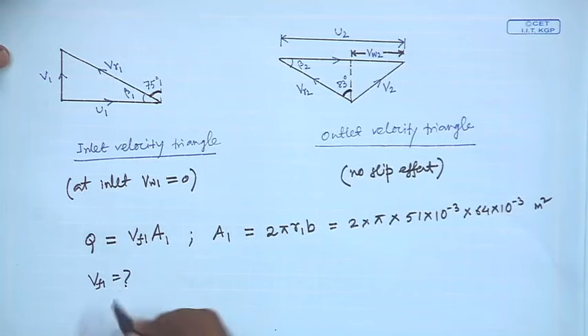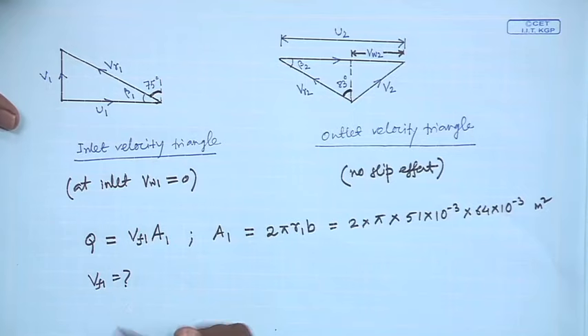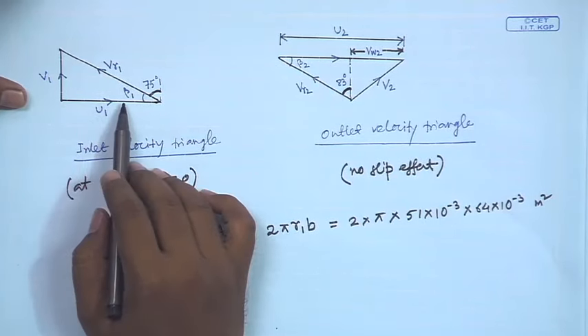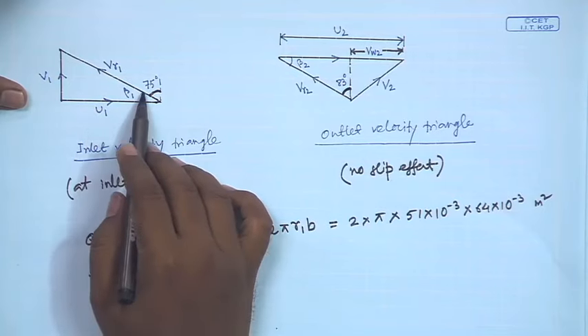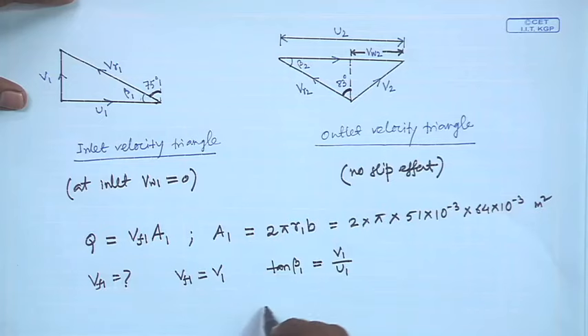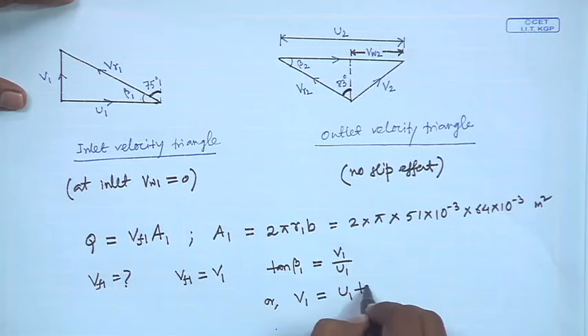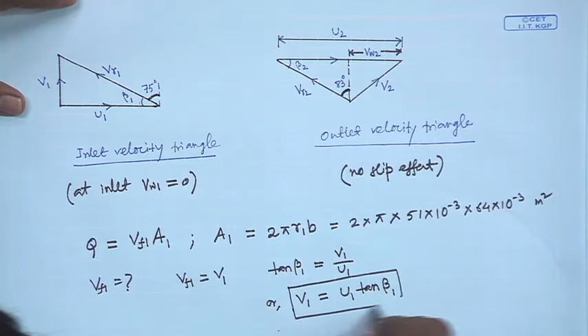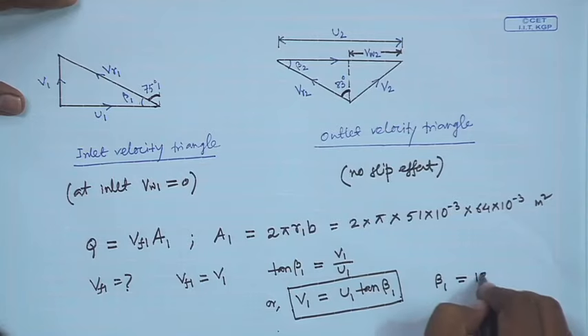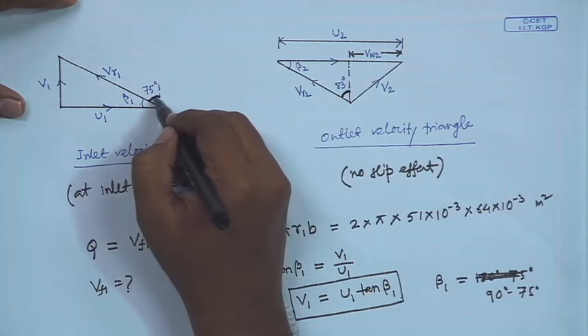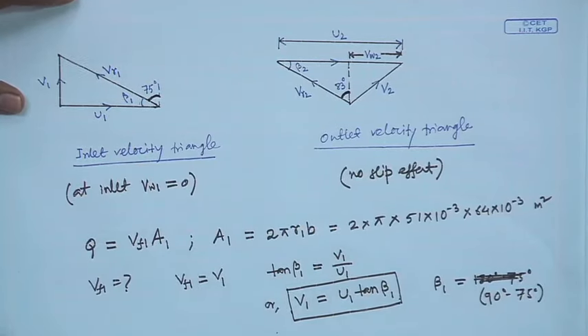Since there is no swirl component, Vf1 = V1. From the velocity triangle, tan(β1) = V1 / u1, so V1 = u1 × tan(β1). Beta1 is 90° minus 75° = 15°. u1 is the peripheral velocity at inlet, calculated as π × d1 × n / 60 = π × 2 × 51×10⁻³ × 900/60 = 4.81 m/s.